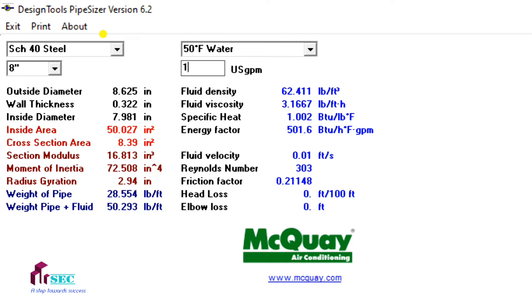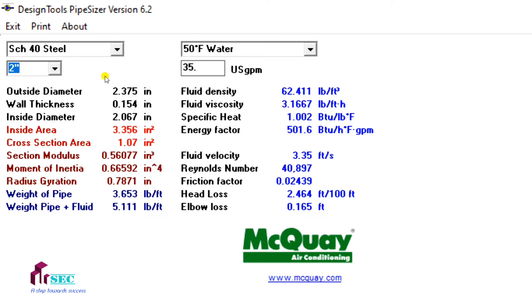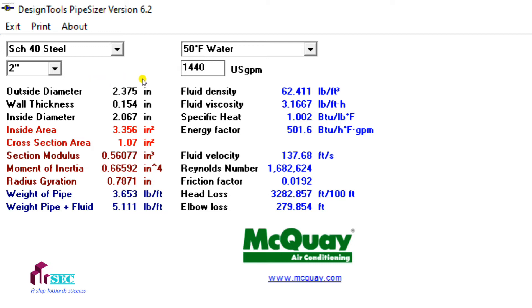Simply enter the GPM as 1440, then select a pipe size — for example, I'm going to select 2 inch — and then look at the fluid velocity; it should be less than or equal to 10 feet per second. You can see the fluid velocity is 137 feet per second, which means this does not meet our condition.